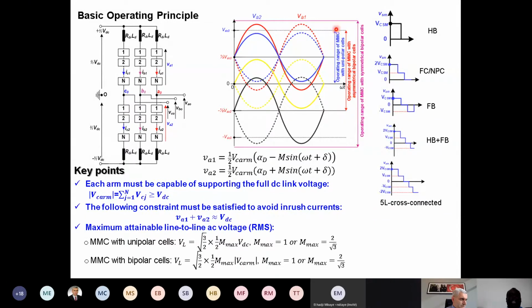And you can create a lot of things in between. And this is just a simple illustration of the implication of different types of cells on the control range, and also the advantage of the MMC with bipolar cells, symmetrical and asymmetrical: it can recreate any DC voltage. As I mentioned before, if you have an MMC with unipolar cells, either this or this, your control range remains the same as the conventional two-level converter, where the DC voltage always has to be positive, and the minimum DC voltage has to be above the peak of the line-to-line voltage at this side.